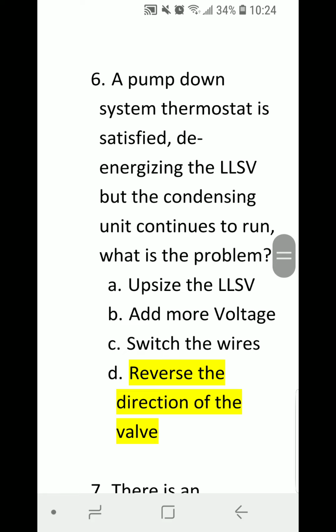Number 6. A pump down system thermostat is satisfied, de-energizing the liquid line solenoid valve, but the condensing unit continues to run. What is the problem? A. Upsize the liquid line solenoid valve, B. Add more voltage, C. Switch the wires, or D. Reverse the direction of the valve. Correct answer is reverse the direction of the valve.